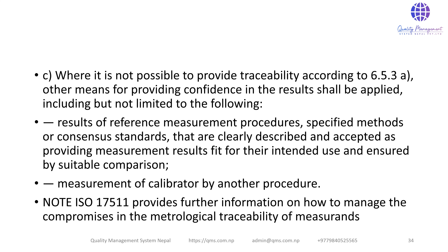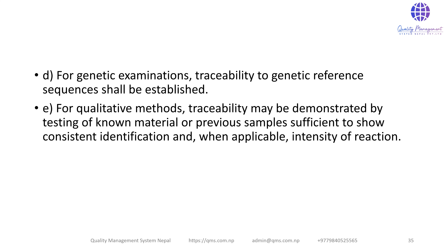Where it is not possible to provide traceability as above, other means for providing confidence in the results shall be applied, including results of reference measurement procedures, specified methods, or consensus standards clearly described and accepted as providing measurement results fit for their intended use, verified by suitable comparison measurements. Note: ISO 17511 provides further information on managing compromises in metrological traceability. For genetic examinations, traceability to genetic reference sequences shall be established. For qualitative methods, traceability may be demonstrated by testing of known material or previous samples sufficient to show consistent identification and, when applicable, intensity of reaction.